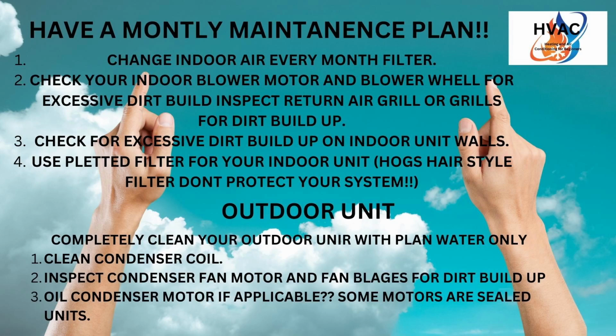So you're going to wash the condenser and make sure your blade motor and fans are clean, and make sure the surroundings around that condenser are clean and free of grass, debris, and weeds. Also, right before you clean it, once you're done cutting, get your yard blower and blow away all that stuff you've cut, so when the unit kicks on it doesn't try to pick some of that up off the ground - because it can attempt to do so, I've seen it happen. So blow or rake it out of the way, then commence your cleaning.